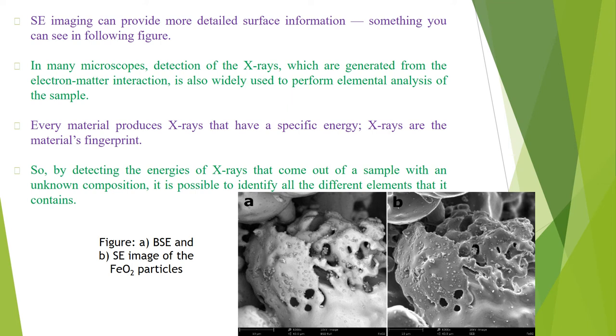Secondary electron imaging can provide more detailed surface information, as seen in the following figure. In many microscopes, detection of X-rays generated from the electron-matter interaction is also widely used to perform elemental analysis of the sample. Every material produces X-rays that have a specific energy — X-rays are the material's fingerprints. By detecting the energies of the X-rays that come out of a sample with an unknown composition, it is possible to identify all the different elements that it contains.